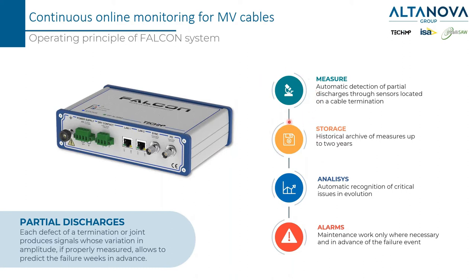By measuring the partial discharge activity we are at the same time measuring the condition of the joints and terminations of the cables. This device not only performs the measurement but also saves it — there is a built-in memory able to save measurements and then plot graphs. Because of these graphs it's possible to make analysis, and if a defect is identified and worsening, an alarm will be issued so operators will be informed by Falcon.